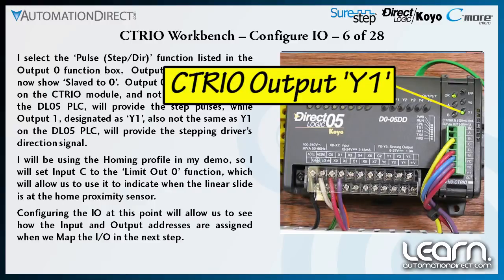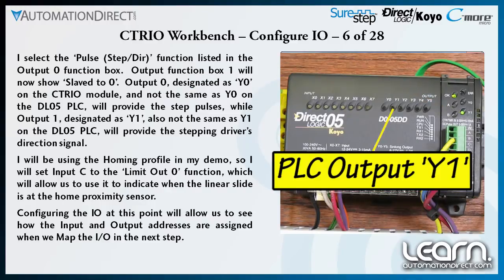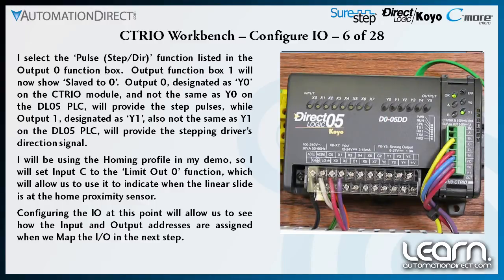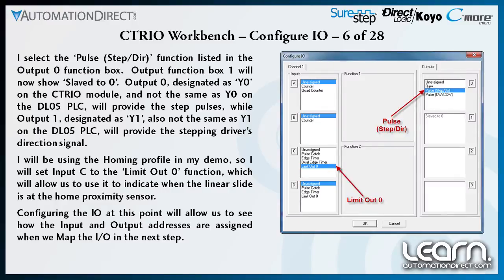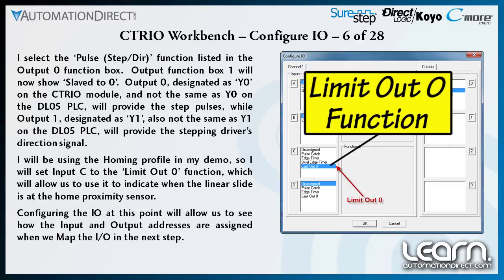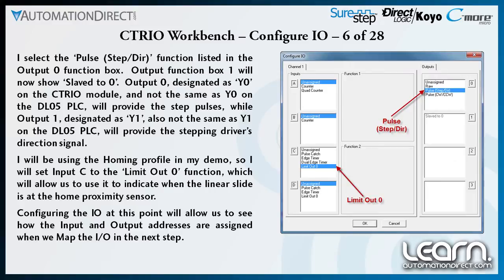Output 1, designated as Y1 — also not the same as Y1 on the DL05 PLC — will provide the stepper drive's direction signal. I will be using the homing profile in my demo, so I will set input C as the Limit Out 0 function, which will allow me to use it to indicate when the linear slide is at the home proximity sensor. Configuring the I/O at this point allows me to see how the input and output addresses are assigned when I map the I/O in the next step.